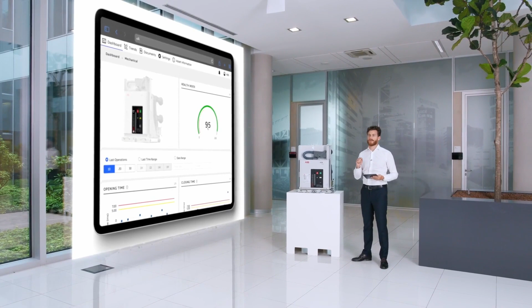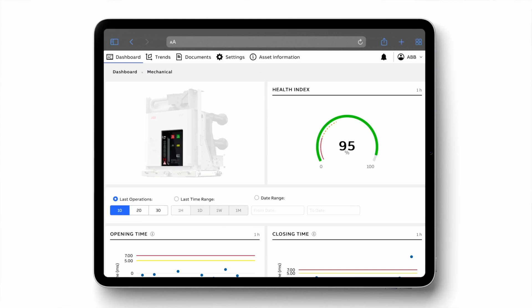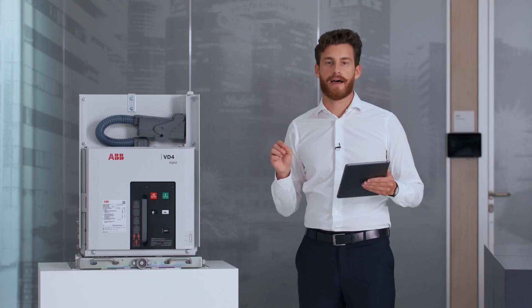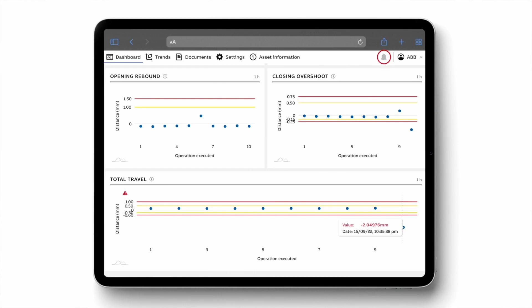With VD4 Evo, however, the check is relentlessly done on each breaker operation, and all the parameters are benchmarked against the proper design references specific to the single unit characteristics. In case of anomalies, we indicate a possible root cause and suggested action, but there's also the option of directly contacting an expert in case of a permanent message, so to get a fast and focused solution in few steps.